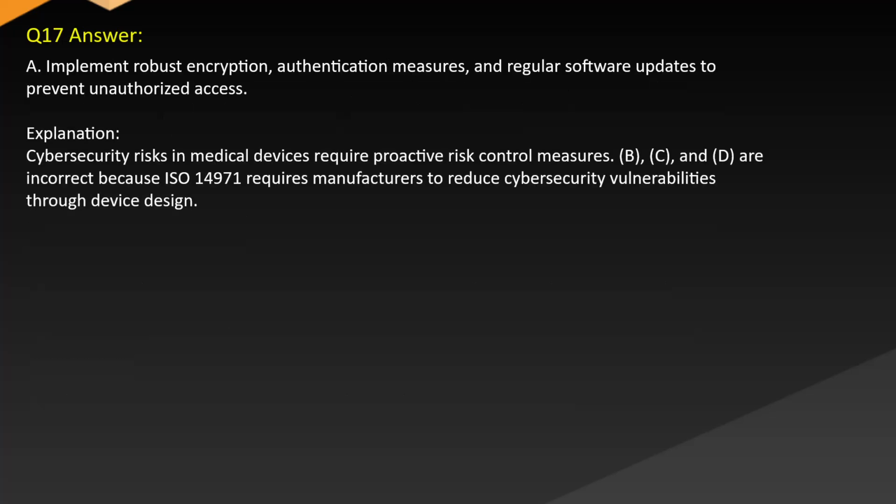Answer A. Implement robust encryption, authentication measures, and regular software updates to prevent unauthorized access. Explanation: cybersecurity risks in medical devices require proactive risk control measures. B, C, and D are incorrect because ISO 14971 requires manufacturers to reduce cybersecurity vulnerabilities through device design.